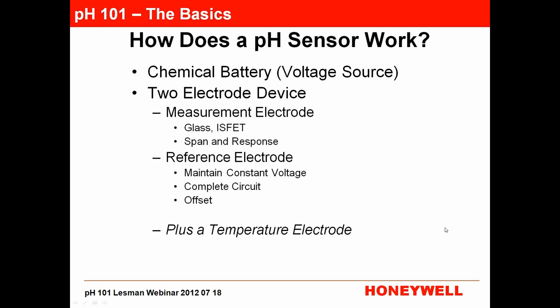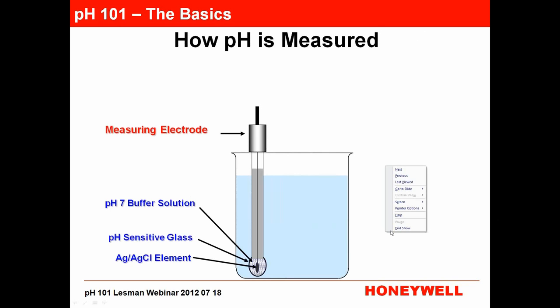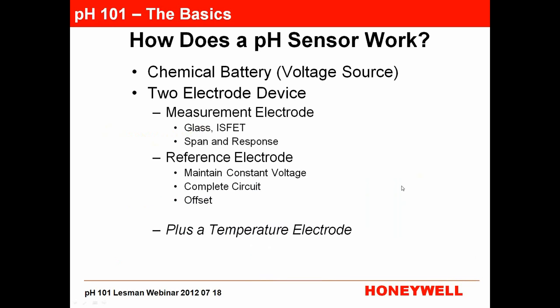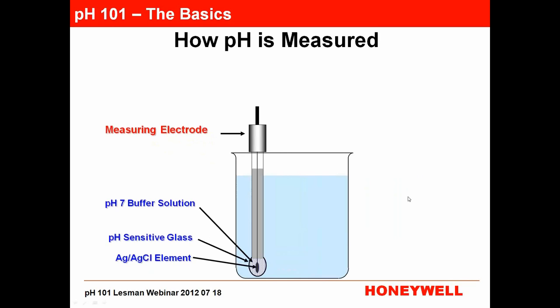If your sensor creeps up slowly when moving between buffers, that's a response issue — also related to the glass measuring electrode. The other electrode is the reference electrode, which maintains a constant voltage to be compared to the varying voltage on the measuring electrode, and it completes the electrical circuit. You have to have both a measuring and a reference electrode to have a complete circuit for current to flow. You'll also have a temperature sensor as well.